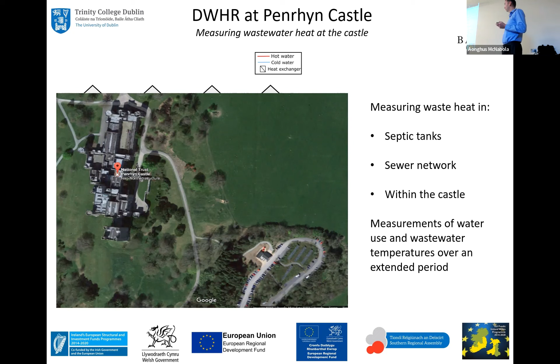So we monitored at various places and ended up settling on the kitchen. The reason was that it has high heat density and we're very close to the point where the wastewater is hot and hasn't lost its temperature. Another important practical factor is that we're quite close to the heating system, so if we recover this heat we need to do something with it - it has to be integrated into the existing heating system. If those two things are far apart, we'll lose heat along the way.